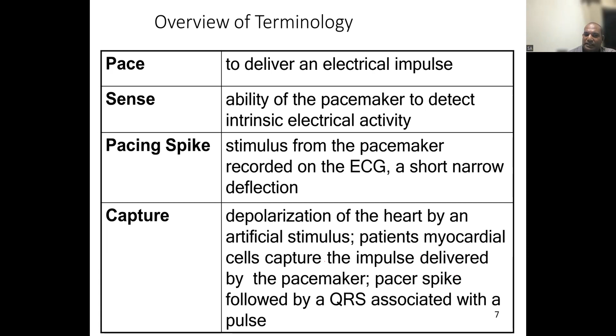Pacing threshold is a concept where we try to understand what would be the minimum current that we need to deliver to the patient to capture the heart. So that also means any current above that level will pace the heart. But we like to know what is the minimum current. The reason is we don't want to waste the battery of these pacemakers. For example, if it's a temporary pacemaker system, that's okay. You can replace the battery. But in case of permanent pacemakers, you have to be very careful with the battery life.